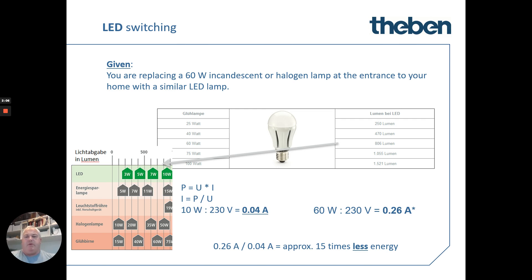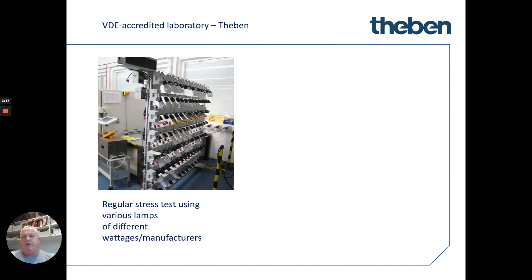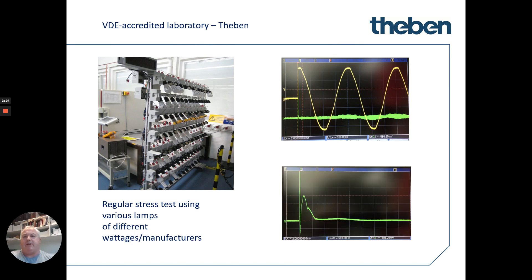So Theben, with typical engineering brilliance, decided to test some of their fittings and some market fittings to see exactly how these come out. What they ended up doing is rigging up a full lab with an oscilloscope, looking at the inrush currents of LEDs and measuring the wattages compared to the startup currents of a lot of popular LEDs and even some of their own.